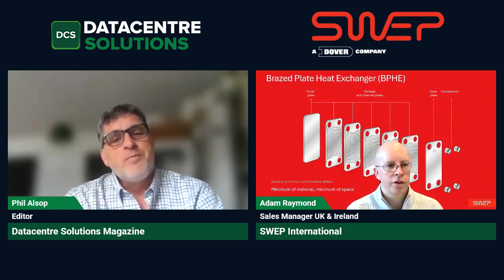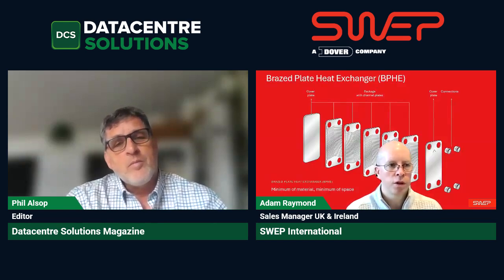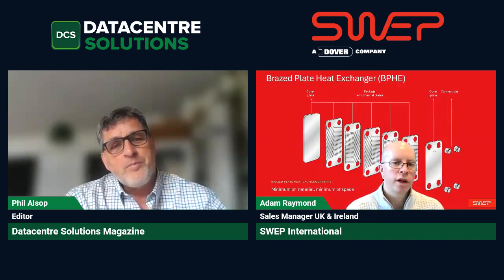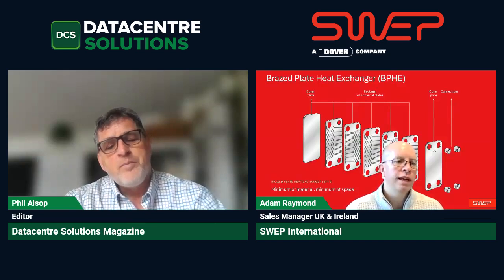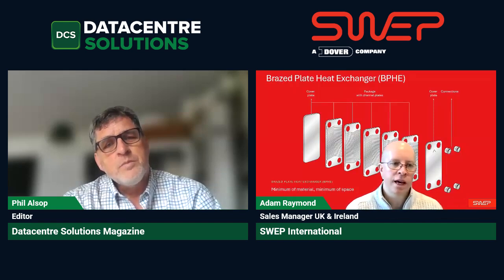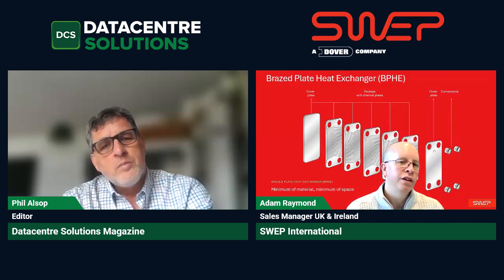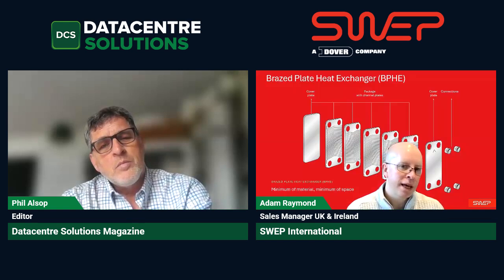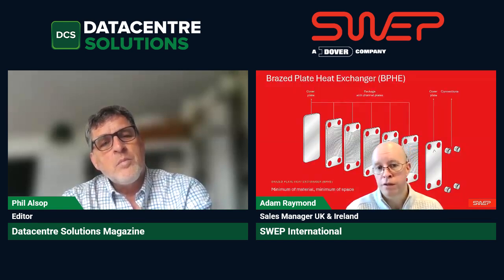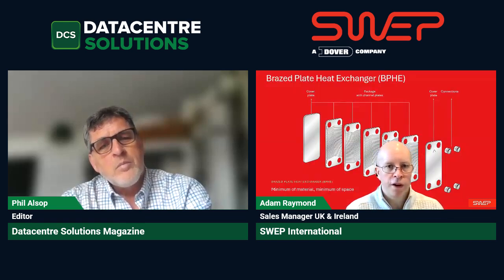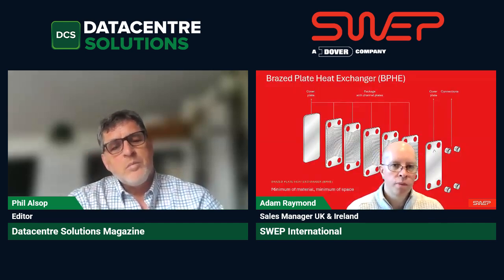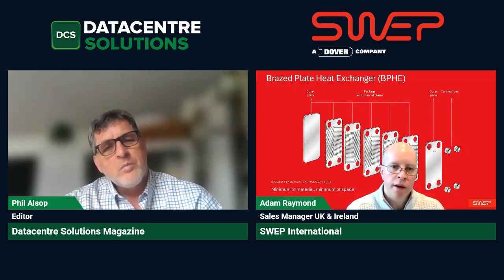What we see is quite a demand now for our products to be used when we're transferring heat from one fluid to another. We don't lose any energy, but we have to step down the temperature from the inlet to the outlet, so we can't get perfect temperature transfer. We see a demand for this and we can get very close. But the closer we get to the inlet and outlet temperatures being the same, we need a much bigger heat exchanger for the same given duty. So we're seeing a lot of demand for these very tight temperature profiles, which means we need a bigger heat exchanger. We're having to really look at the product range more closely and optimize more designs. This is more on the water-to-water liquid cooling side.